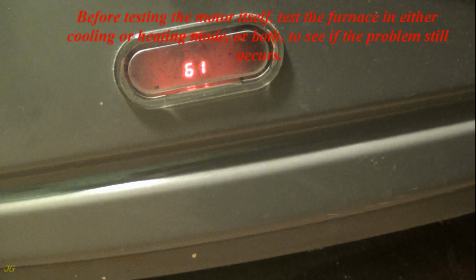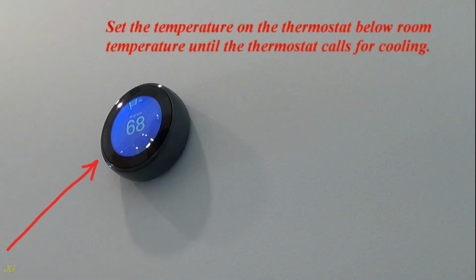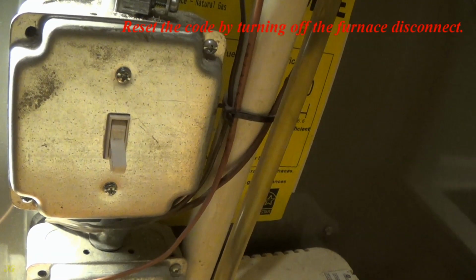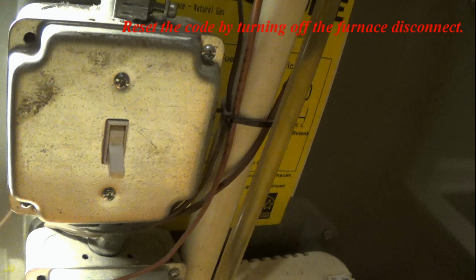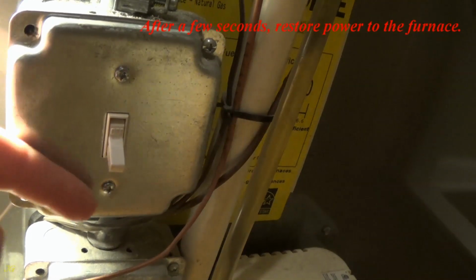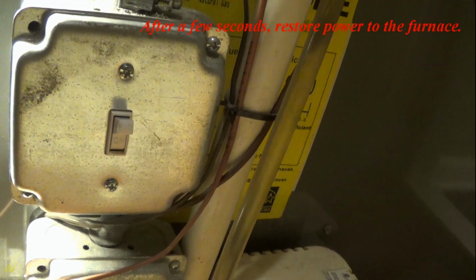Before testing the motor itself, test the furnace in either cooling or heating mode, or both, to see if the problem still occurs. Testing in cooling mode. Set the temperature on the thermostat below room temperature until the thermostat calls for cooling. Reset the code by turning off the furnace disconnect.